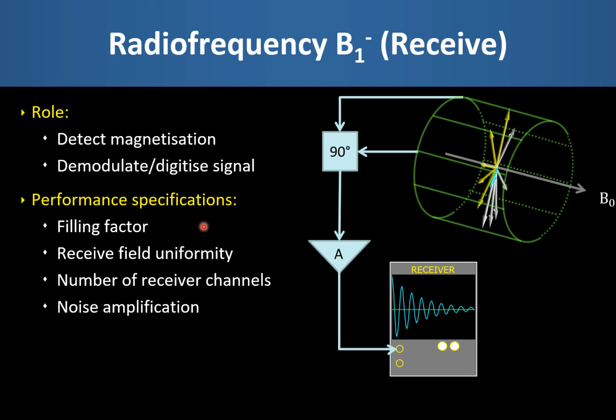However, each coil element must be connected to its own separate receiver channel, and then the images from each receiver need to be finally combined. The receive chain should also minimize the amount of noise amplification. This has led to manufacturers digitizing the signals closer to the coil elements, and in some cases actually including the analog to digital converters into the coil design, and then converting the signal to optical for transfer to the reconstruction computer.